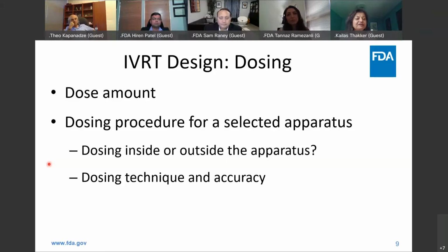Because for most of the current manufacturers of the equipment, I think you need to have at least a minimum of 300 to 400 milligrams of the dosage form to have complete coverage of the area of exposure. So 100 milligrams seems low to me. Yes, but if they have some custom designed apparatus and they have complete coverage, nothing wrong with it.